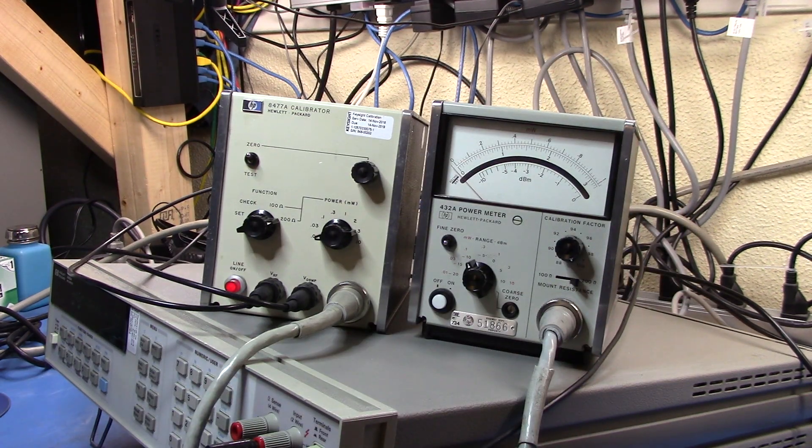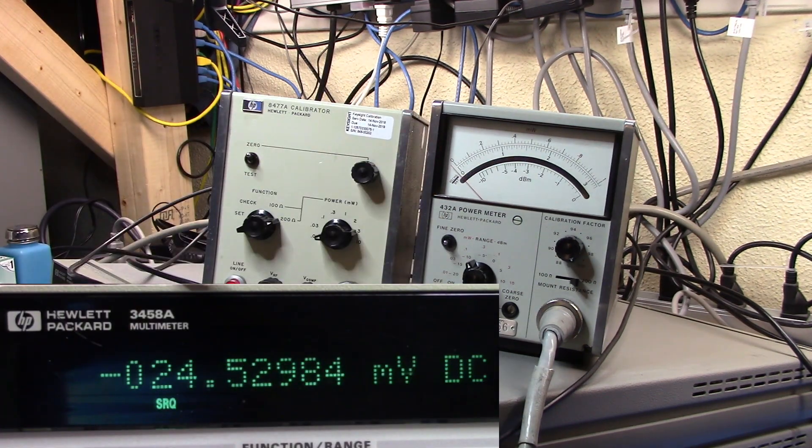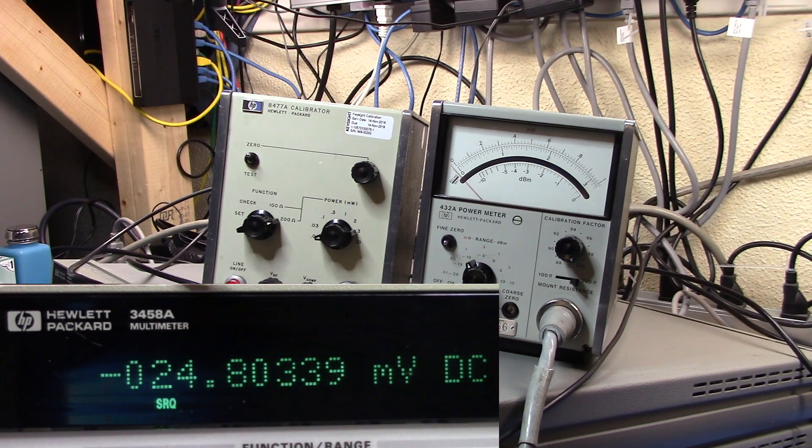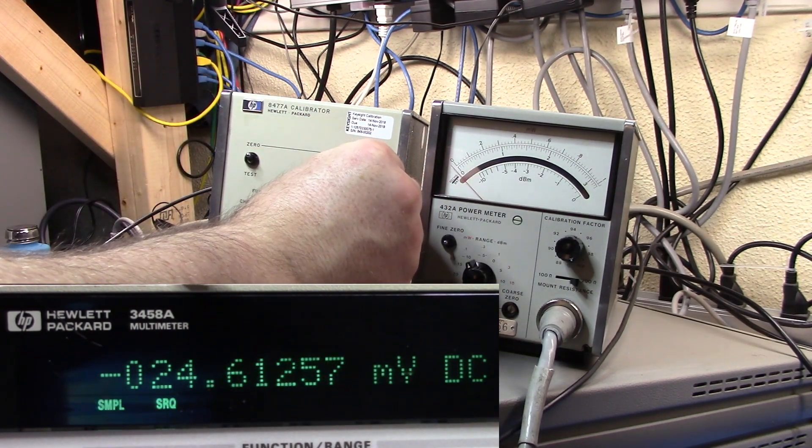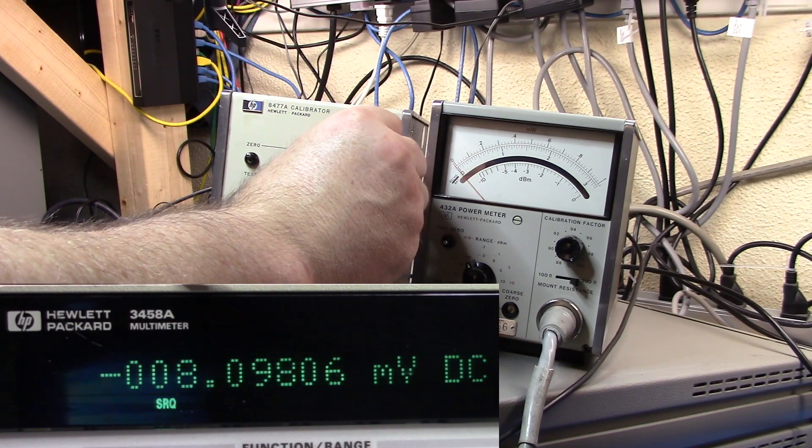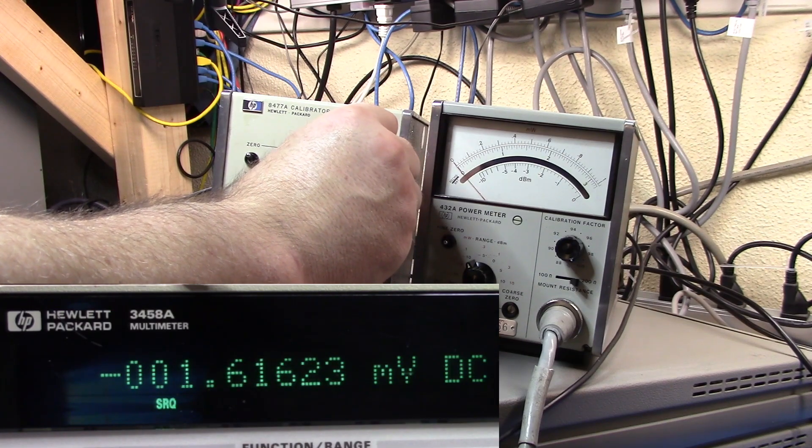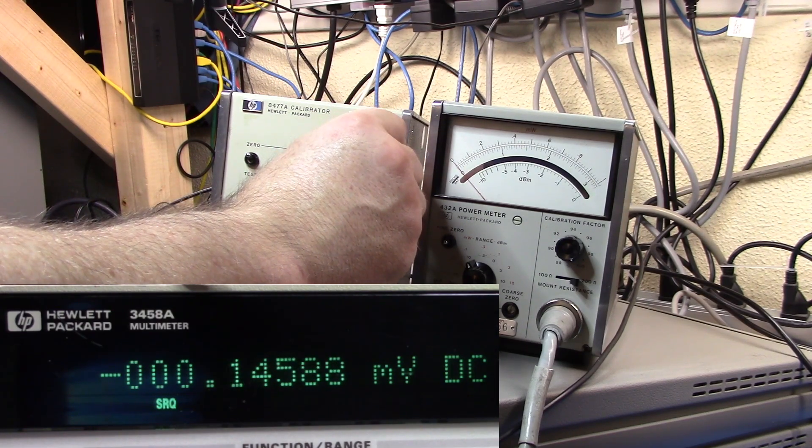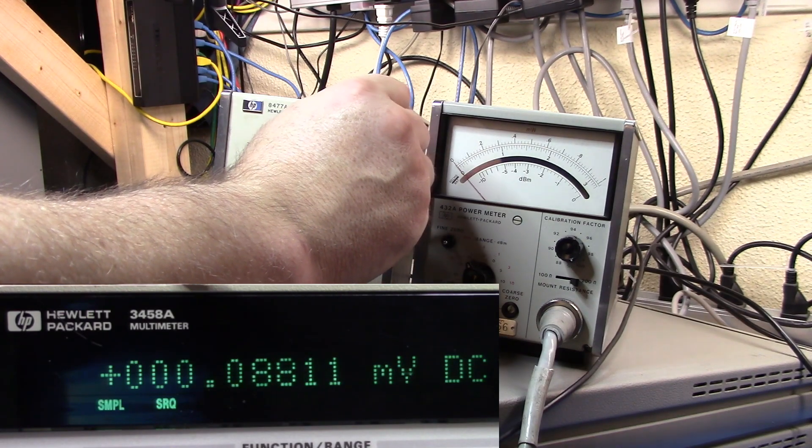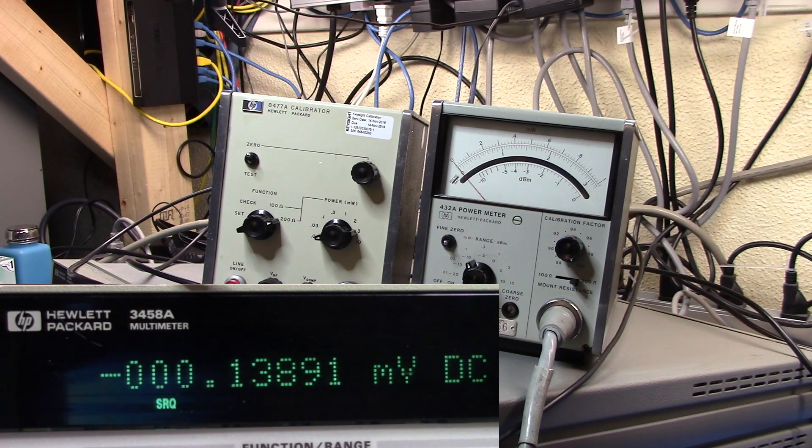Now we need to adjust the zero knob here until we get zero volts plus or minus two millivolts. So let's go and do that. We'll keep going down. Ideally you'd want to be as close to zero as you can get and there we go. We're at zero millivolts plus or minus two.